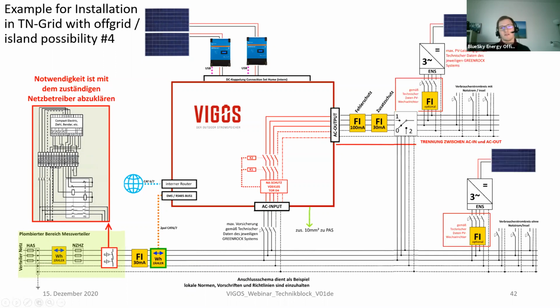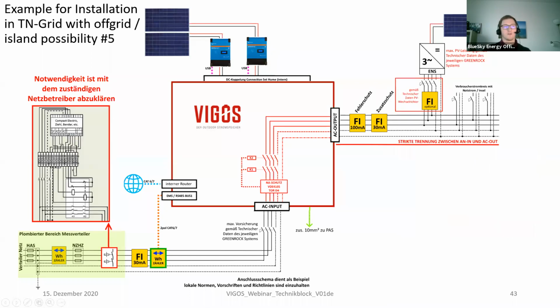So that means you can just combine all the functions together: do a DC coupling for black start, do the AC coupling of the PV for a higher PV power, and if the customer has more PV available, you can just connect the additional PV here. And just as a recommendation for service cases, please add this switch, so that in case of a service you can connect these loads back directly to the grid. Or what you can also do is connect the whole house on the AC out.